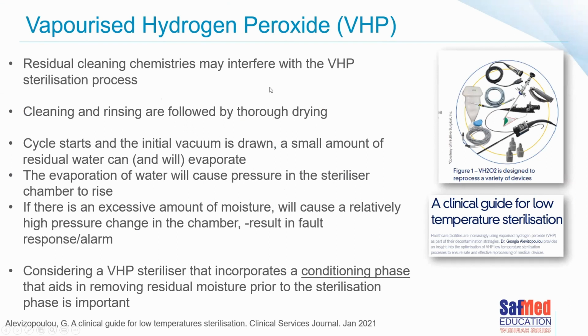The cycle will start with an initial vacuum. When that vacuum is drawn, a small amount of residual water can and will evaporate. It's what we want it to do. The evaporation of the water, however, can cause pressure in the sterilizer chamber to rise. And if there's an excessive amount of moisture, this will cause a relatively high pressure change in the chamber. And that's going to result in a failure or some form of response alarm, pressure too high. And as a result of that, in her article, she goes on to say that considering a vaporized hydrogen peroxide sterilizer that incorporates a conditioning phase, and that conditioning phase that aids in the removal of residual moisture prior to the sterilization phase, is quite important.